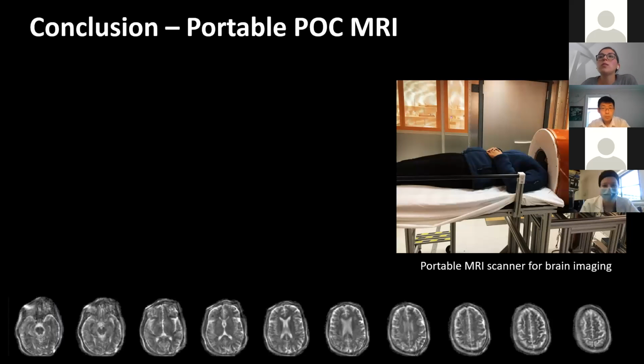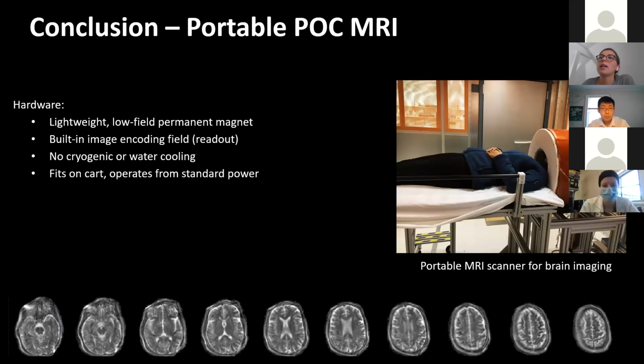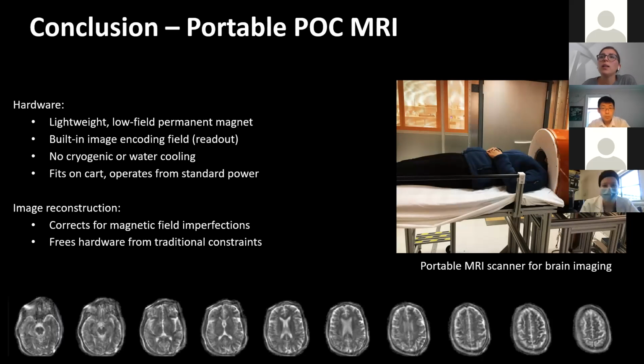So in summary, we've introduced an MRI scanner architecture based on a compact, lightweight, permanent magnet array with a built-in field variation for MRI readout encoding. The system does not require cryogenic or water cooling, and the scanner fits on a small cart and is very portable and operates from a standard power outlet. And we leverage an advanced image reconstruction method to correct for magnetic field imperfections that are caused by the very compact system. And this essentially frees the hardware from some of the traditional constraints of conventional MRI scanners.